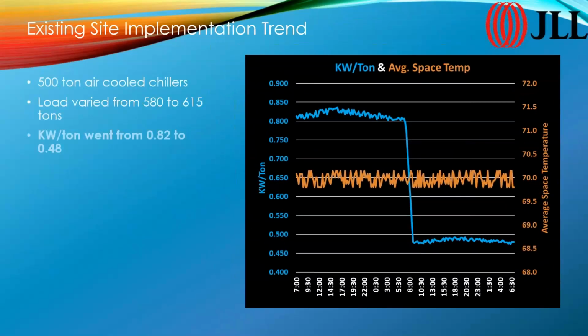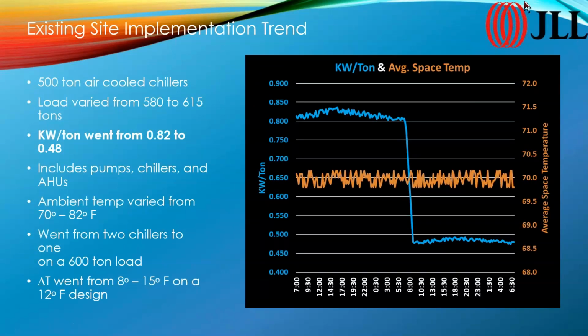And just to come full circle with this, one of the things we're looking at is why we do it and what difference it makes. This is from a data center that we went through, and you can see right around 8 o'clock in the morning, the plant all-in went from around 0.82 kilowatts per ton down to around 0.48. That's the blue line, and the temperature varied somewhere between 68 and 72 on the floor. The ambient temperature during that time went from around 70 to 82. These are air-cooled chillers on this job. The interesting thing about this one was these are 500-ton chillers.